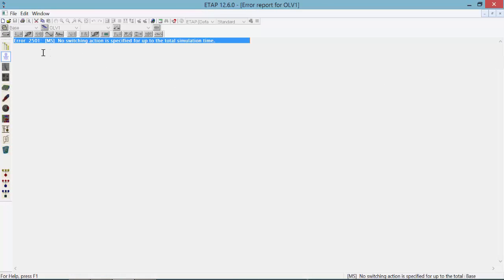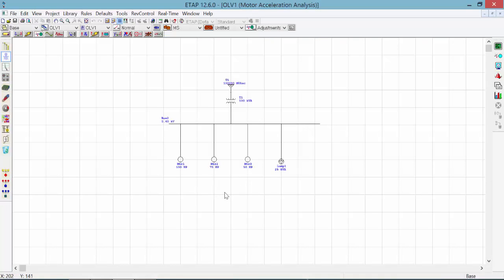We will get an error message which states no switching action is specified for up to the total simulation time. This means in order to run a static or dynamic motor starting analysis, we will need to have a set of events in which we will decide about what loads to be connected to the line at what time. To create those events, move your mouse on the presentation mode toolbar and click on Edit Study Case. Switch to Event tab.